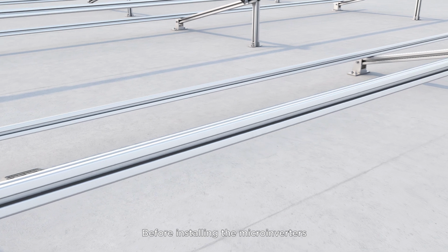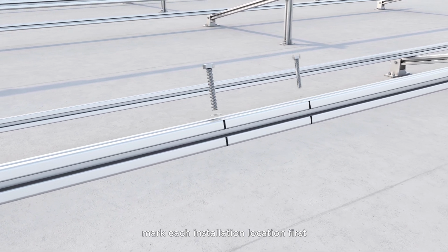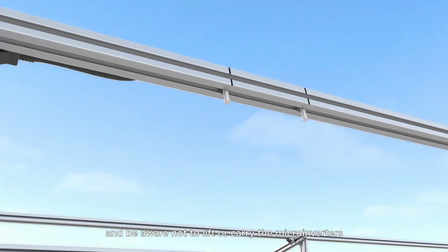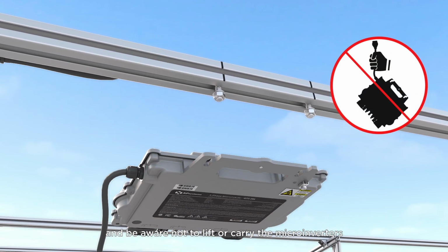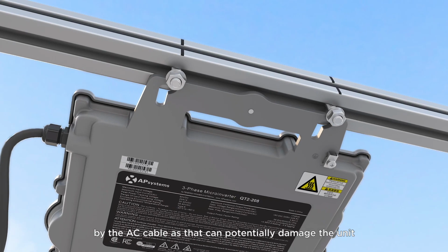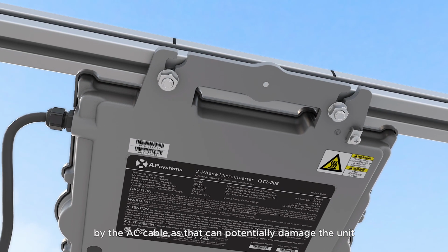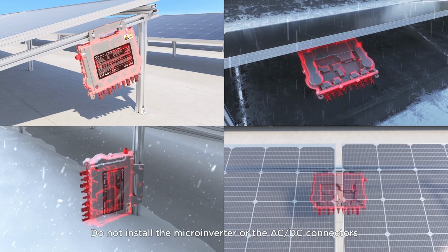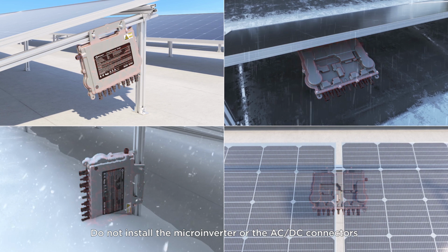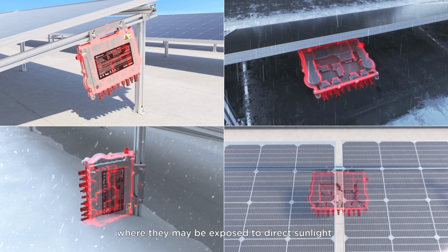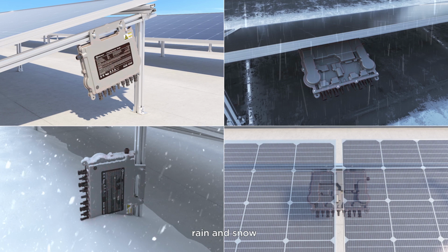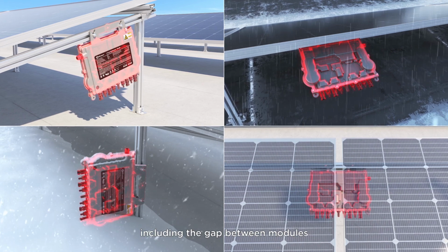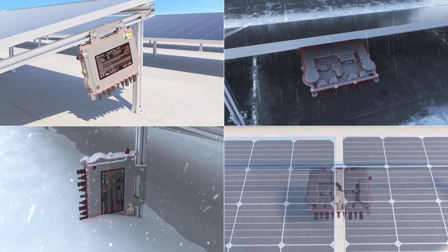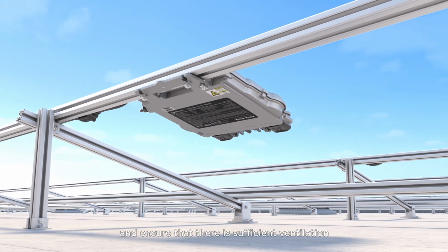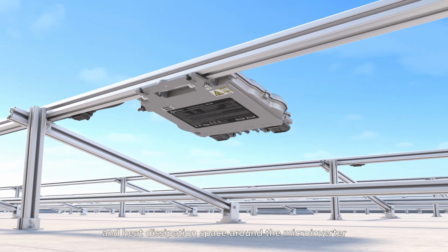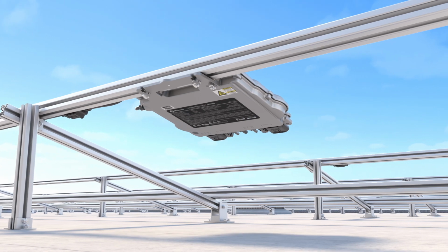Before installing the microinverters, mark each installation location first, and be aware not to lift or carry the microinverters by the AC cable, as that can potentially damage the unit. Do not install the microinverter or the AC-DC connectors where they may be exposed to direct sunlight, rain, and snow, including the gap between modules. And ensure that there is sufficient ventilation and heat dissipation space around the microinverter.